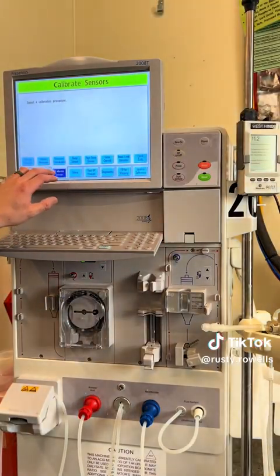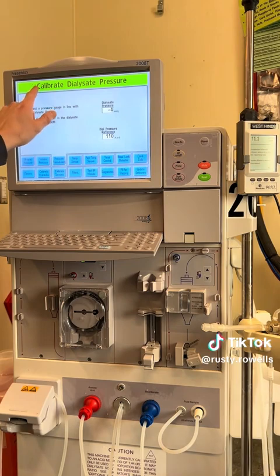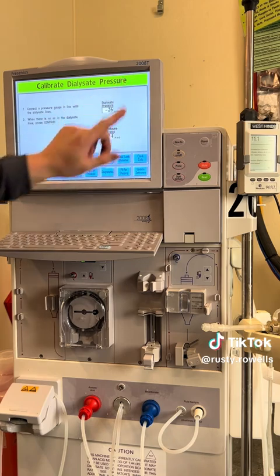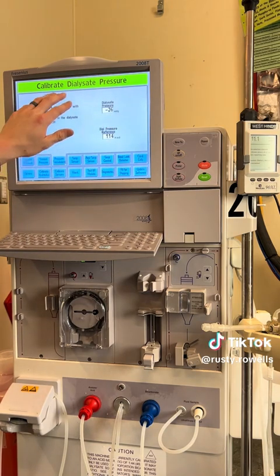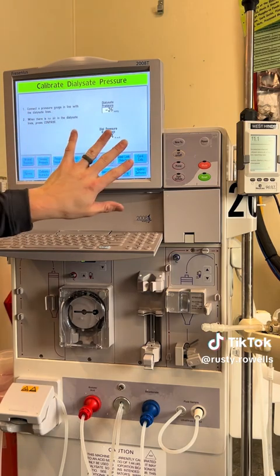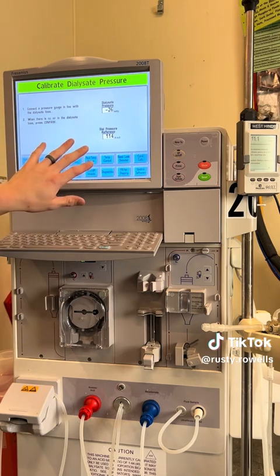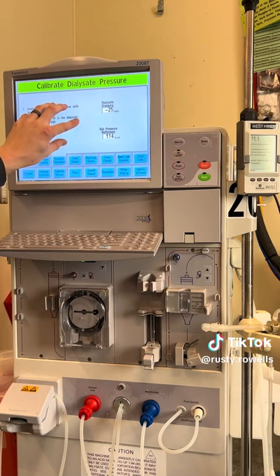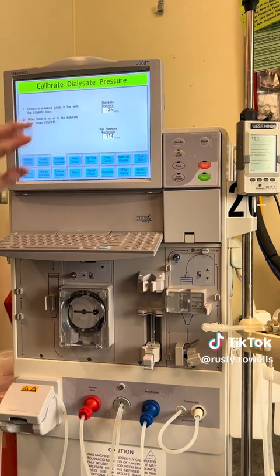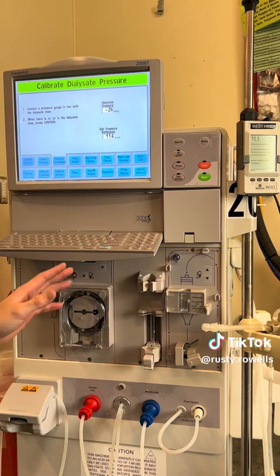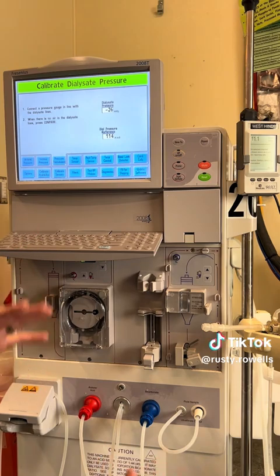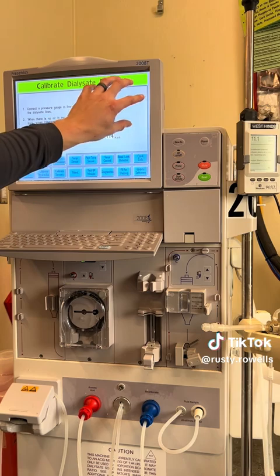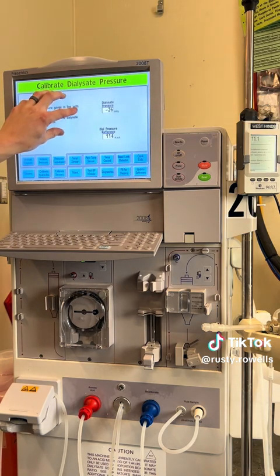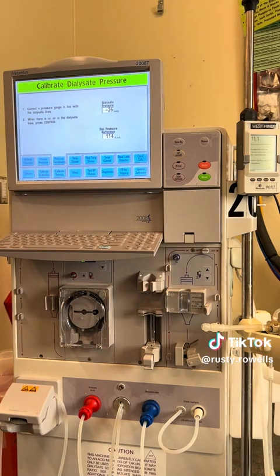And that's the calibration. If you ever do this calibration and you get an operator error message, go back out into dialysis, change your flow rate from an 800 to a 500, hit enter, lock it in, and then come back and do this calibration, and it will work. For some reason, between the 2.72 function software and the 2.74, this machine kind of glitches out and carries over an 800 flow rate into this calibration when it should be carrying over a 500. So I hope this helps better explain things.